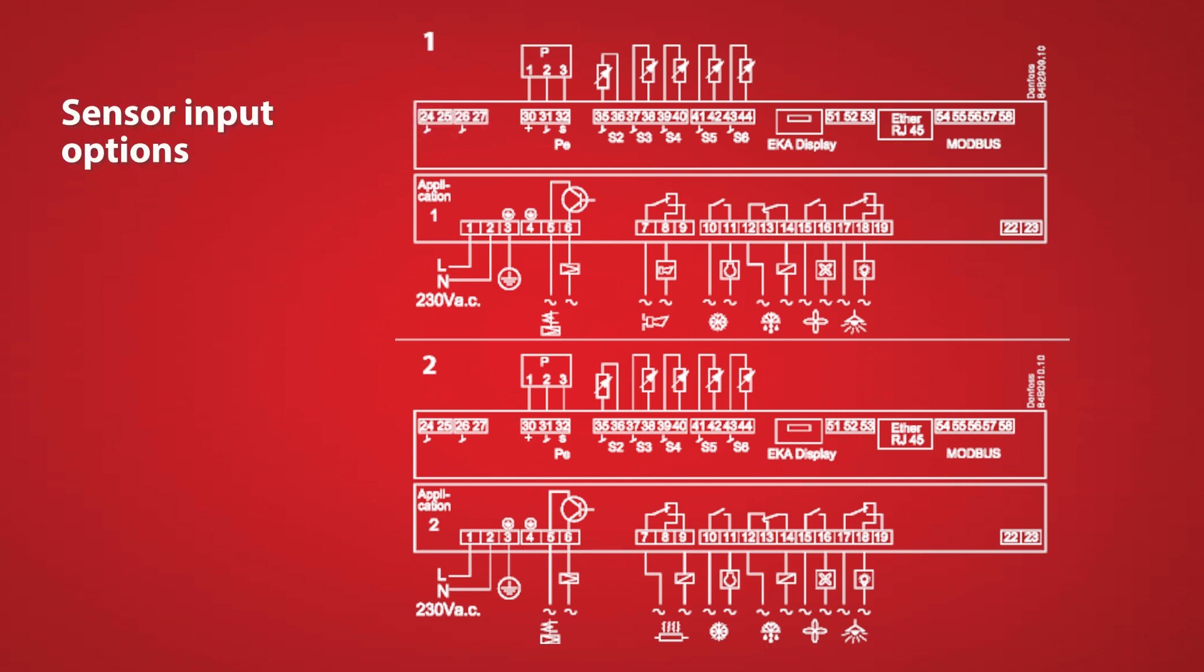Moving down the line we have a pressure transducer here which would be the Danfoss AKS32R pressure transducer used to measure the outlet pressure of the coil. This helps us measure the superheat.